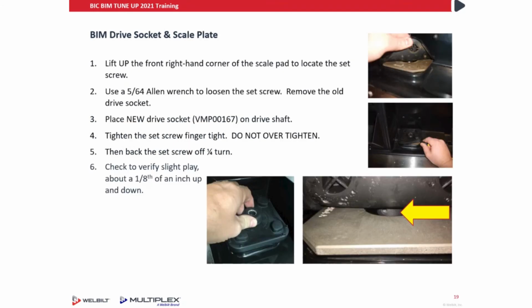Replacing the BIM drive socket. Lift up the front right-hand corner of the scale pad to locate the set screw. Use a 5/64 Allen wrench to loosen the set screw. Remove the old drive socket. Place the new drive socket on the drive shaft. Tighten the set screw finger tight. Do not over-tighten. Then back the set screw off about a quarter turn so that you can verify that you have about 1/8 of an inch play up and down.